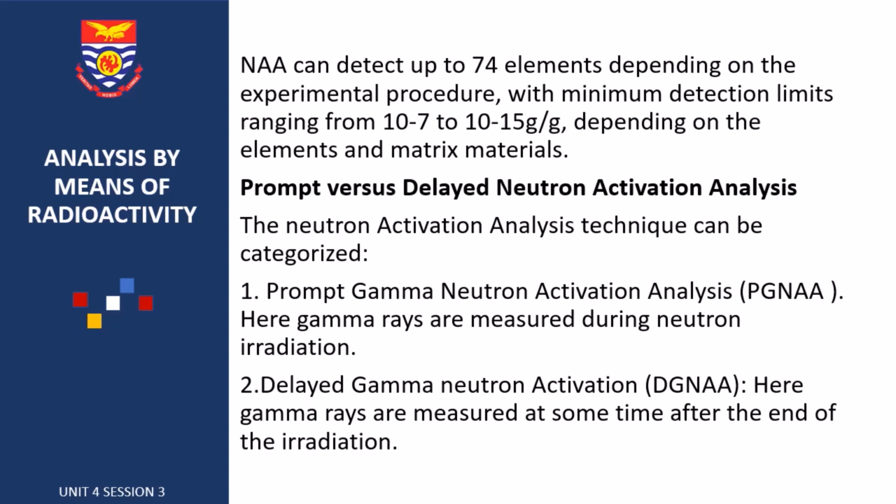And also, elements that produce only stable isotopes, such as lighter elements, can also be measured by the PGNAA. The PGNAA is also applicable to elements with weak decay gamma ray intensities, and 3D and 2D analysis of element distribution in samples can be performed using the PGNAA.